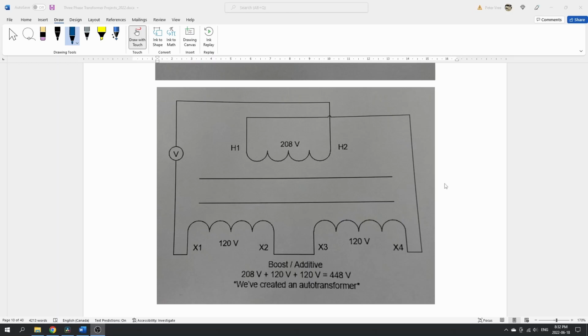I'm looking at this, and there is a difference between what we just did in the lab and this diagram. It's still going to show us the additive voltage, but I should point out the changes. We had a jumper between H2 and X1. Well, in this diagram, I have my voltmeter between H2 and X1. Then we had the voltmeter between H1 and X4. Well, that's where I have the jumper on this diagram. So just to call out that little change, we should still see the additive voltage, but it's not exactly what I had there in the lab.